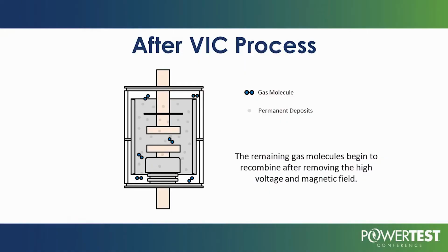After the VIC process, there are still free gas molecules inside the interrupter. We cannot get back to where it was originally, but we continually lower the pressure every time we condition it. This VIC process, this conditioning process, we've conditioned thousands and thousands of interrupters now. We've conditioned every interrupter that's come through our VI shop, our field service people, and the breakers that we sell. We condition new interrupters, used interrupters, old interrupters. We've done this and we've watched the pressures inside for many years, so we have a pretty good idea of what's going to happen.